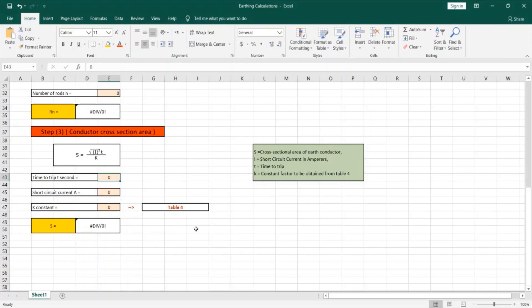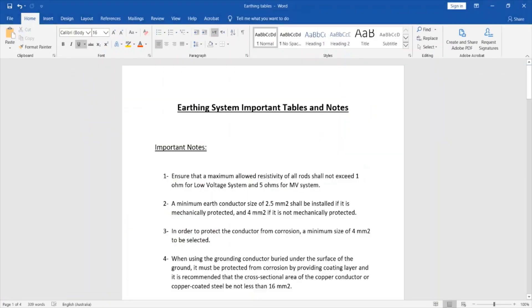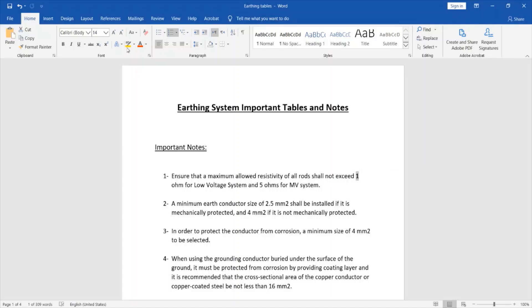Now let me open this Word file that contains reference tables and important design notes. The first note states that the maximum allowed resistivity of all rods shall not exceed 1 ohm. That is important especially for low voltage systems. However, for medium voltage systems, 5 ohms is the allowed target resistivity to be achieved.